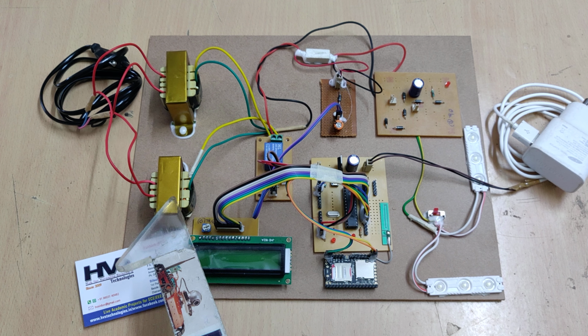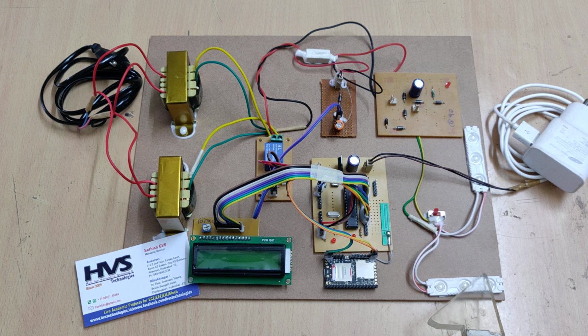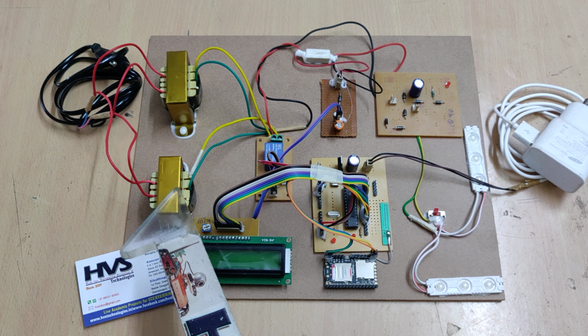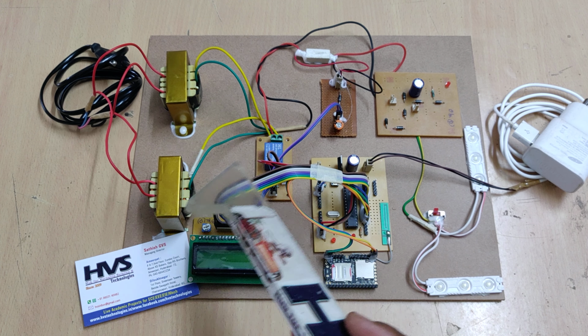Considering this is the primary transformer and the secondary transformer, whenever the load increases, in order to protect the primary transformer, we add this in parallel, so that the load will be shared between these two transformers, and that sharing is done with the help of this electromagnetic relay.